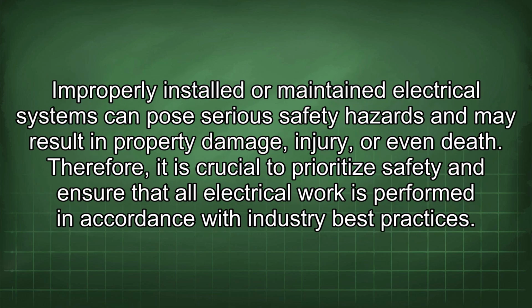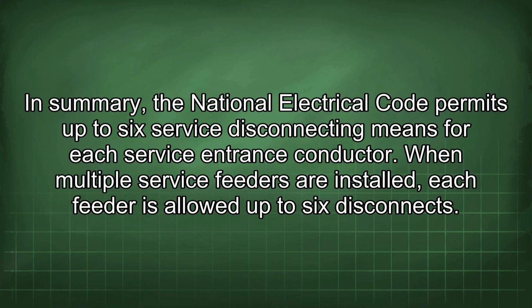Improperly installed or maintained electrical systems can pose serious safety hazards and may result in property damage, injury, or even death. Therefore, it is crucial to prioritize safety and ensure that all electrical work is performed in accordance with industry best practices. In summary, the National Electrical Code permits up to 6 service disconnecting means for each service entrance conductor. When multiple service feeders are installed, each feeder is allowed up to 6 disconnects.